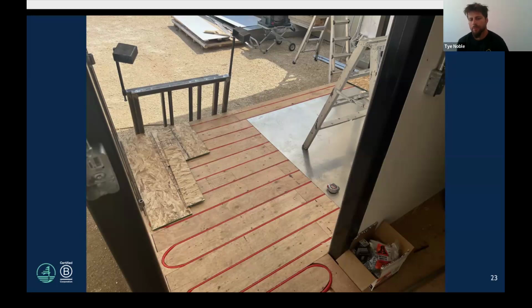There's three different pumps: one turns on when the kitchen needs heat, one turns on when the hallway needs heat, and one turns on when the exterior needs heat, which it never really does, but it's a useful way to cool down the generator rather than blowing it out a radiator. Those are just off-the-shelf Grundfos hydronic circulating pumps.